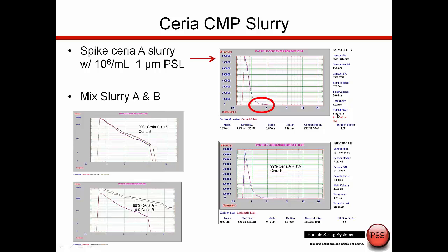And I want to point out here we're counting on the order of millions of particles. To really do this consistently, we want to count hundreds of thousands to 1 million particles. And there's really no issue here because we can still do this in just a couple of minutes. Since we can work at higher concentrations, we can generate this kind of data, collecting hundreds of thousands to millions of particles in measurements that take just a few minutes.